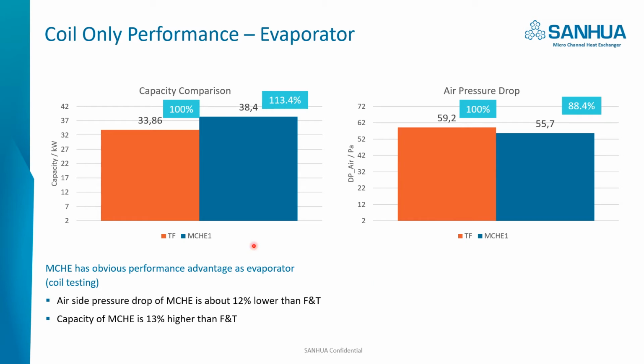Then we compare the performance as an evaporator. This is still the coil-only performance testing. The left chart shows the capacity comparison. Microchannel heat exchanger is about 13% higher than the 4-row fin tube heat exchanger. And the right side is about air side pressure drop. The microchannel heat exchanger is about 12% lower than the fin tube heat exchanger.